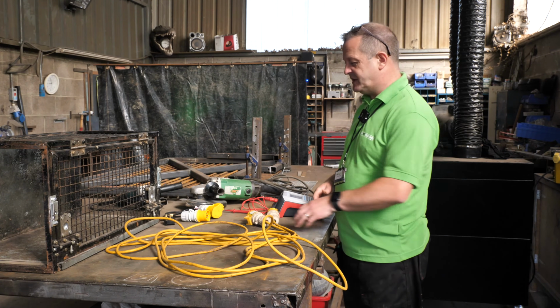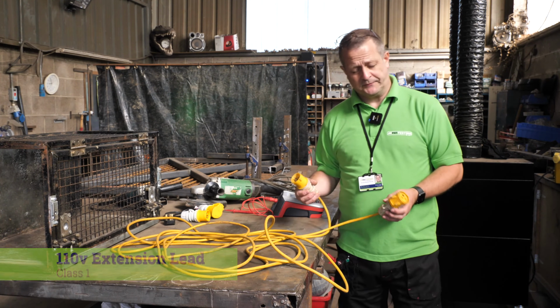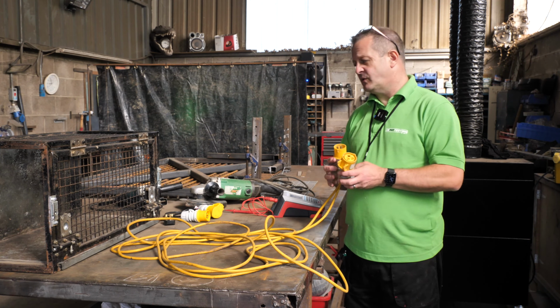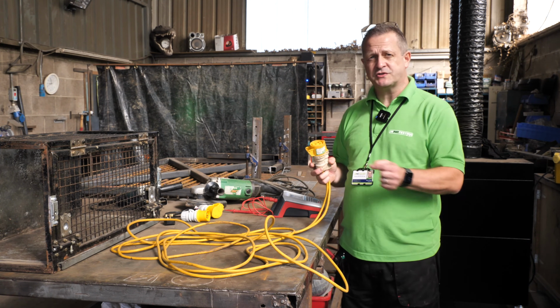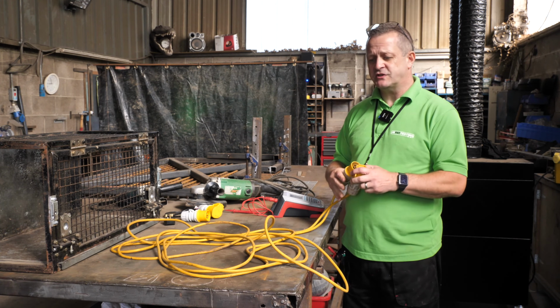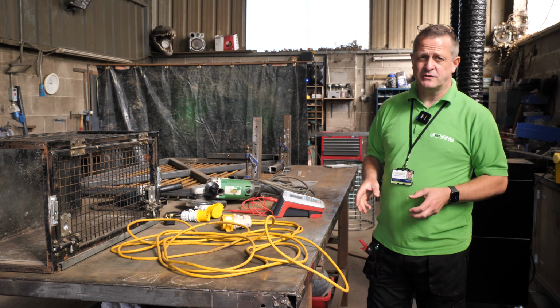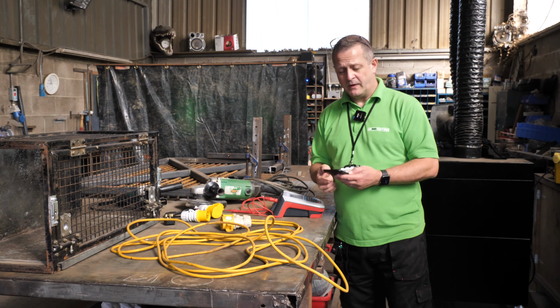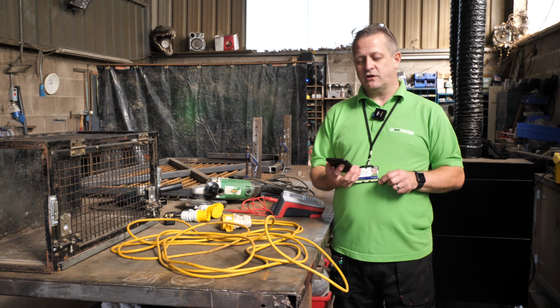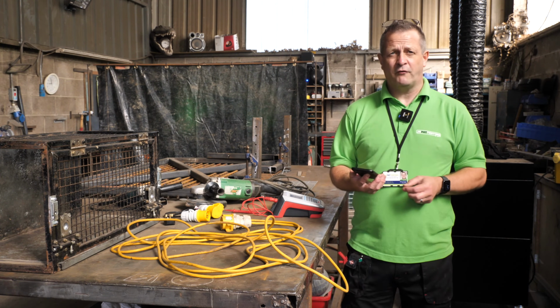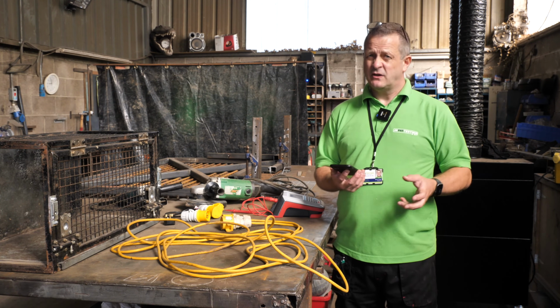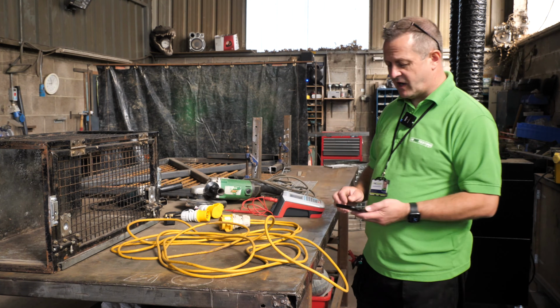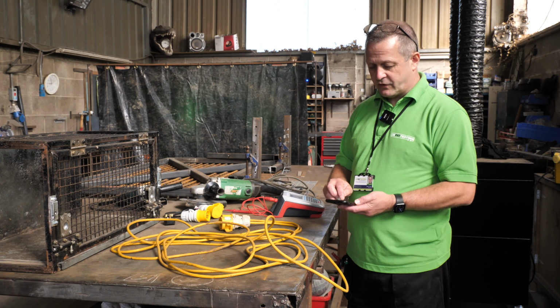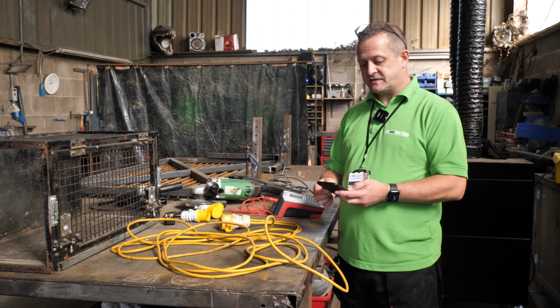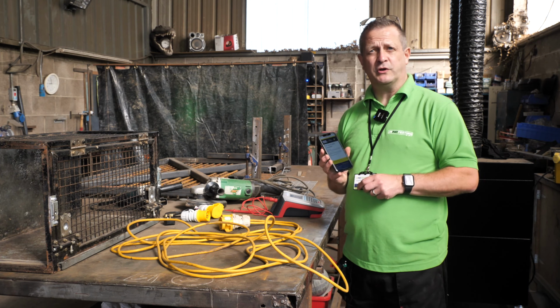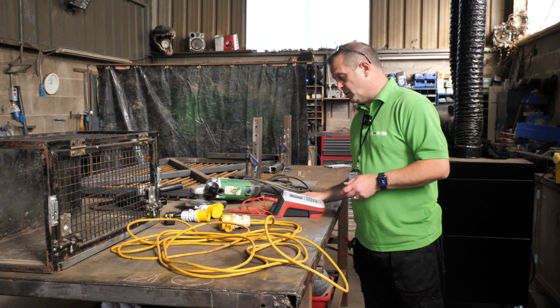So we're now going to look at testing this 110 extension lead. And with flexible cable, we need to work out from the length and the CSA, the cross-sectional area of cable, the resistance level. Now, there is a mathematical equation with that. However, I like to keep things simple. And a quick Google of a PAT testing earth limit calculator will bring back a number of websites where you can just put in the details just to make your life easier. So I've already pre-measured this cable and I know it's 12 meters long and the cross section is 2.5. So that's telling me that the earth pass mark should be no more than 0.2 for it to achieve a pass. So that's what I'm going to be working towards.